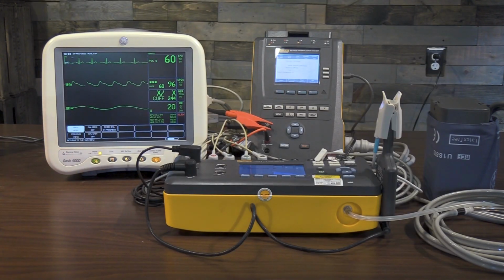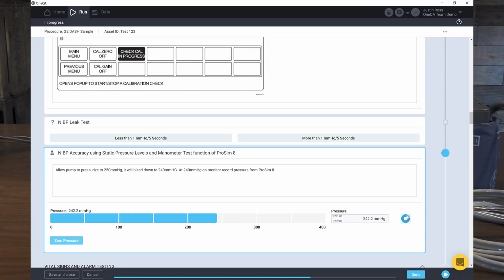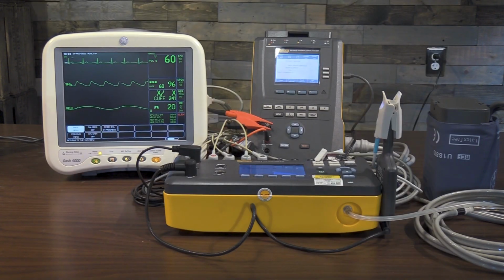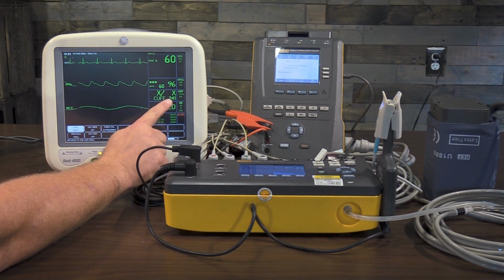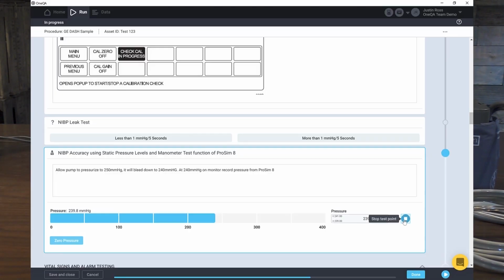So we pumped up to 250, and it's going to bleed down to 240. When it says 240 here, we're going to push the stop button. And if the pressure is within tolerance, which is plus or minus 1 millimeter mercury, we'll get a pass. If it's outside that, we'll get a fail. So we're at 241. Wait till this goes to 240. It's bleeding down, a little bit more to bleed down here. There's 240, so I'll push the button here. And my pressure was within 1 millimeter mercury. So 240 here, 239.8. Spot on.